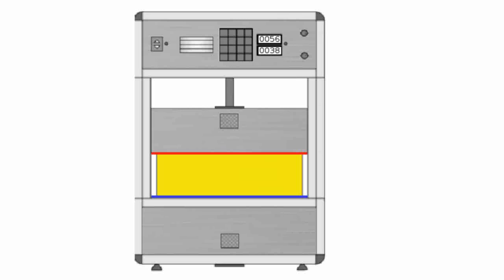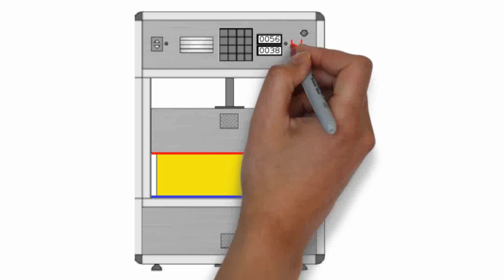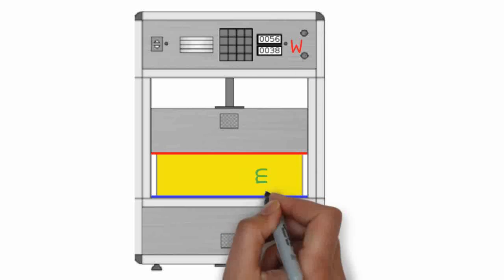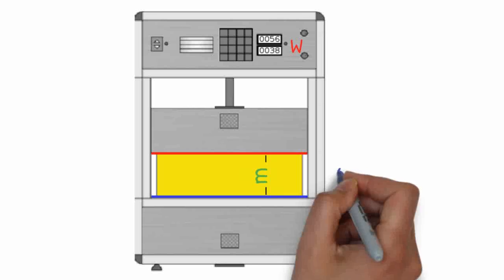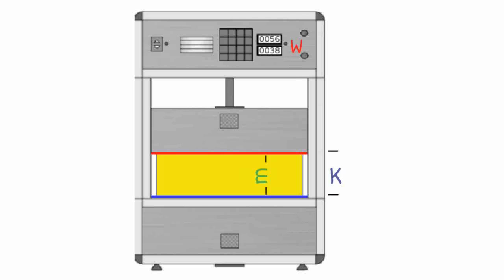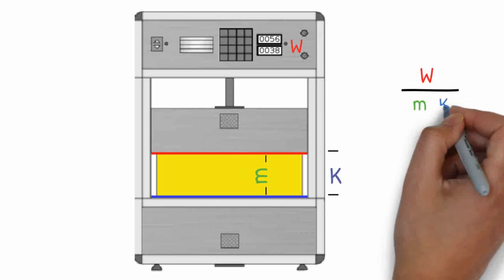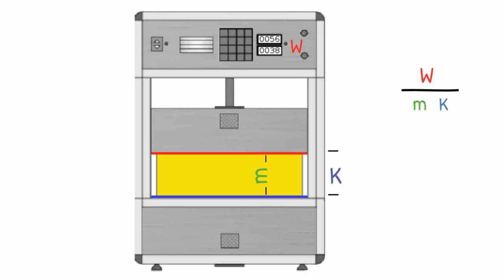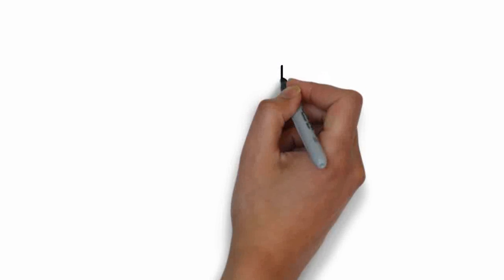Thermal conductivity can be measured with an apparatus like this, where a specimen is put between plates of a different temperature. In simplified terms, the heat as it is traveling through the specimen is recorded, and if the distance and the temperature differential are known, it is possible to calculate the thermal conductivity from this, which is given in watt per meter Kelvin. To give you an idea of magnitude, vacuum insulation panels start at about 0.004 watt per meter Kelvin.